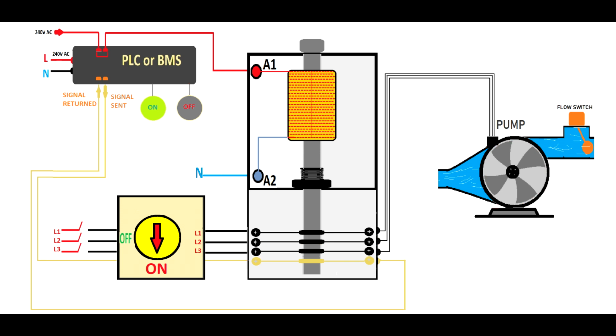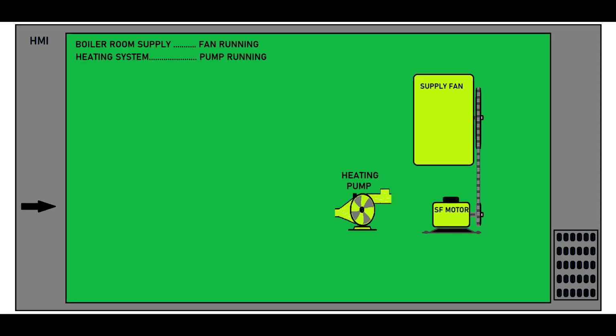Let's see what happens if the circuit breaker pops up because of a malfunction. If the circuit breaker pops up, the signal is still running despite the power circuit being interrupted. And guess what the guy who is remotely monitoring the system on his laptop will see on his front end panel. As far as he's concerned, the pump is running.